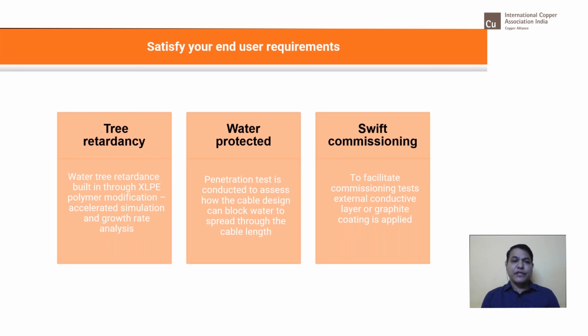When I was in the Middle East, all the utilities like DEWA and ADWEA were asking for the tree retardancy test on the completed cable. Normally, the tree retardancy test is on an XLPE compound, before the manufacturing, and it has to be tested to ensure the enhanced properties of cross-linked polyethylene, so that they can offer superior reliability and longer performance in high stress cable designs. It has to be done at the component level, as I said, but some utilities can ask to do it on the completed cable as well.